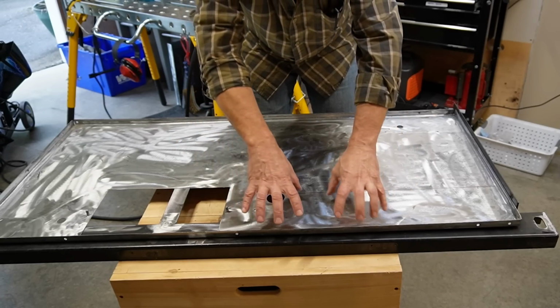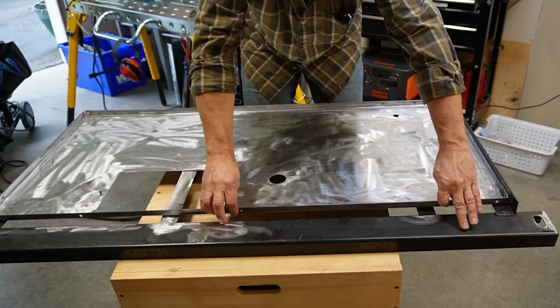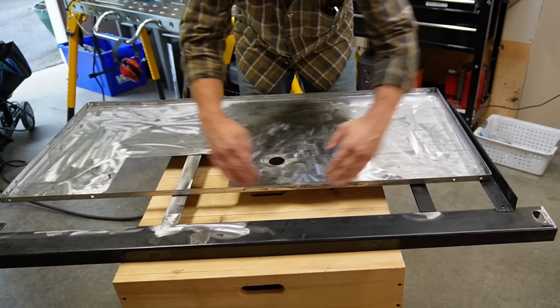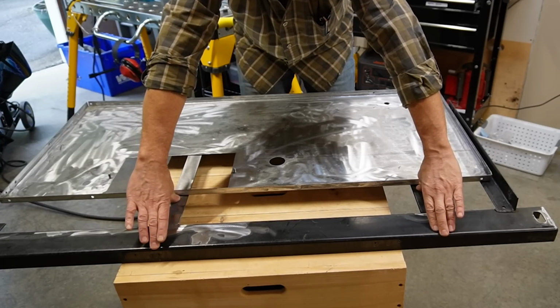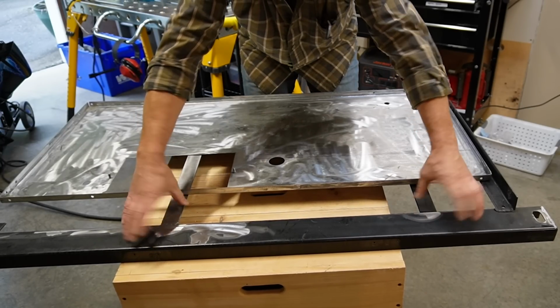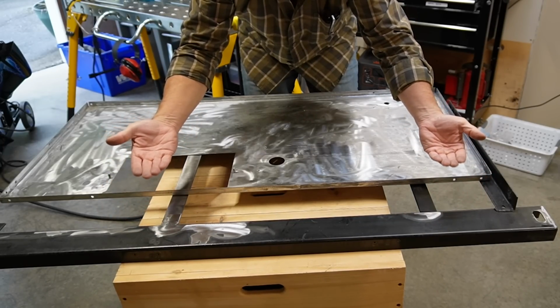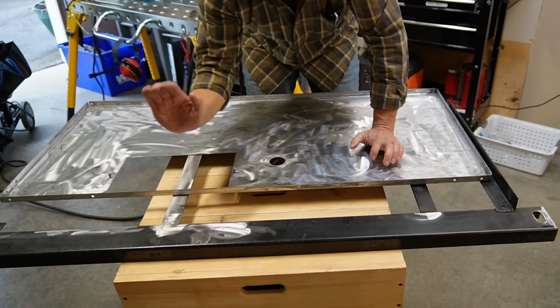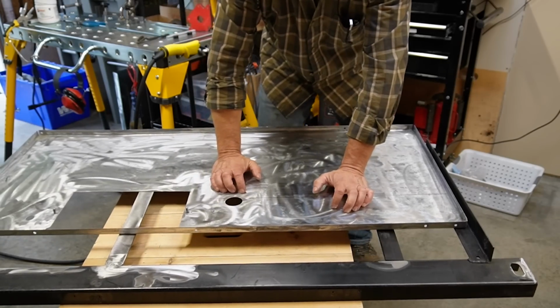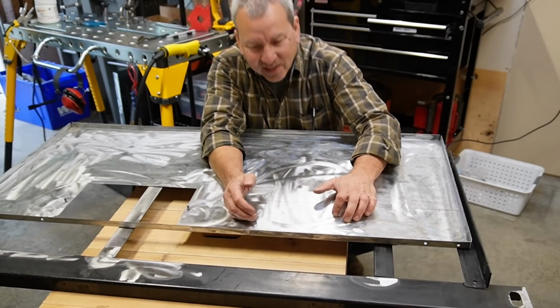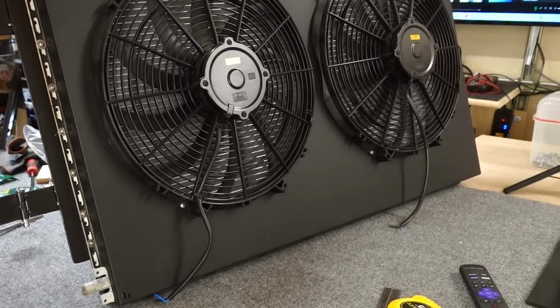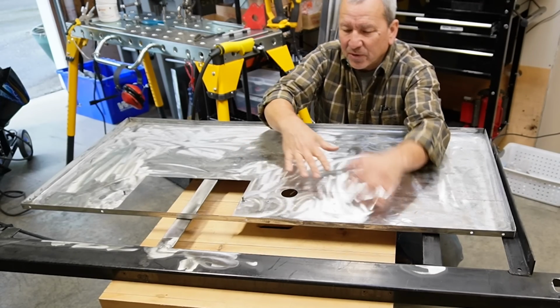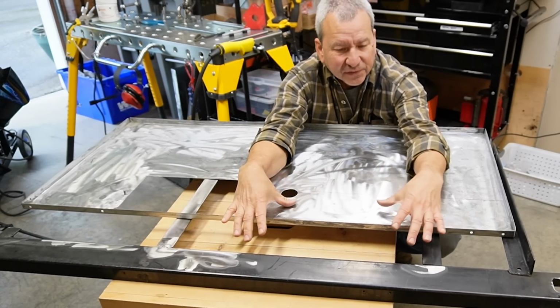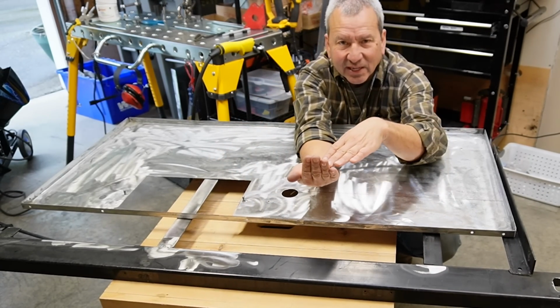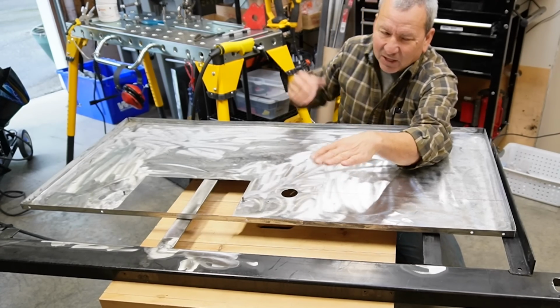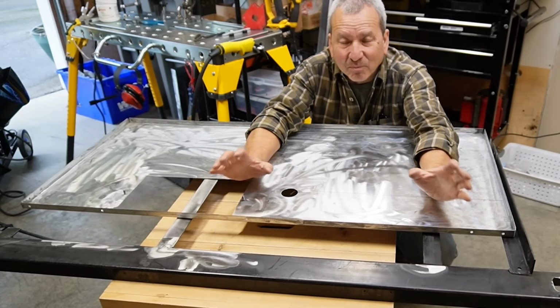What I'm going to do to the front of the support system is cut it, and I want this front support beam to be about 3 inches higher, so it's going to be a little L-shaped thing. The reason is the large condenser unit is now going to be angled slightly underneath this whole thing, so by lifting this a little bit, it creates more space for me to angle it down and below.